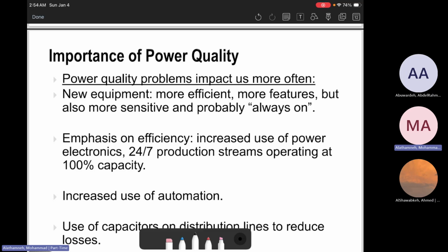So we need to focus on the efficiency. And again, when there is a huge usage of power electronics, this will have impacts. They are working 24/7, which leaves less tolerance for interruptions. It can also impact automation: we have the PLC, variable frequency drives (VFDs), SCADA, anything with logic. All of them can be impacted by a bad waveform.